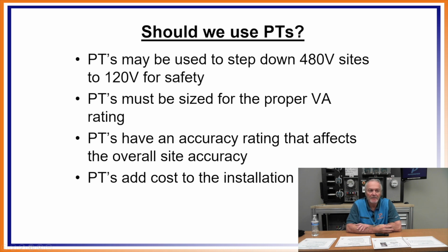They go off of power. That's how they're rated. As you remember, we covered that before, and they've got some of those wacky designations, a little bit wackier. Of course, the CTs are a lot simpler than the PTs in how they designate it using the letters. But the PTs have an accuracy rating that affects the overall site accuracy. That's exactly right. Remember, I'm adding in the inaccuracy of the PT, but I'm also making it safer and easier to work with at the bottom of the pole. And they do add cost. They do add cost to the installation.